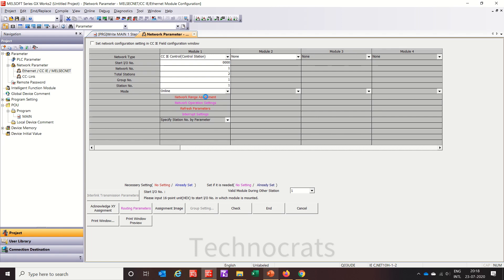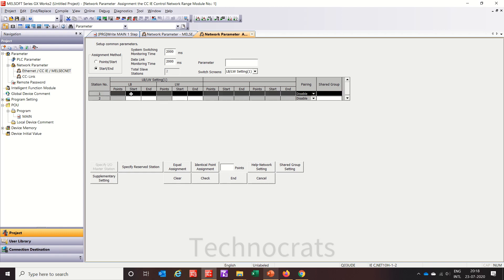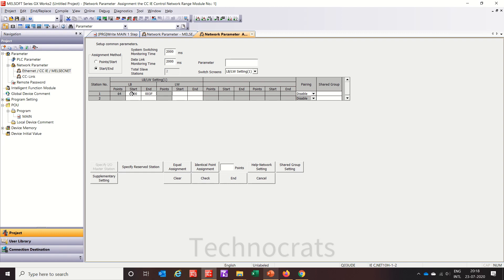Now let's move to network range assignment. Here we have LB and LW — this is for station number 1. I will put 0 and 3F, which covers 64 points. Further, I will use F for 16 points. For the second station, that will be 40 and 7F for 64 points, and 10 to 1F for 16 points. So this is the setting.